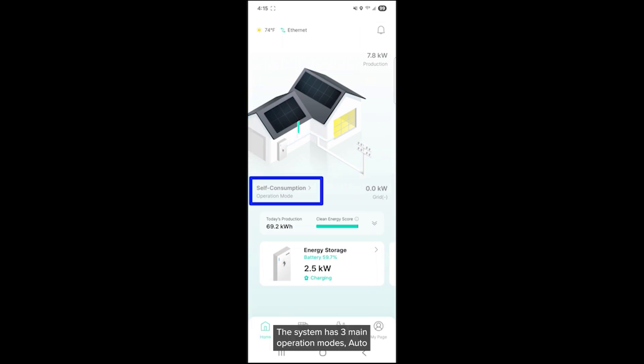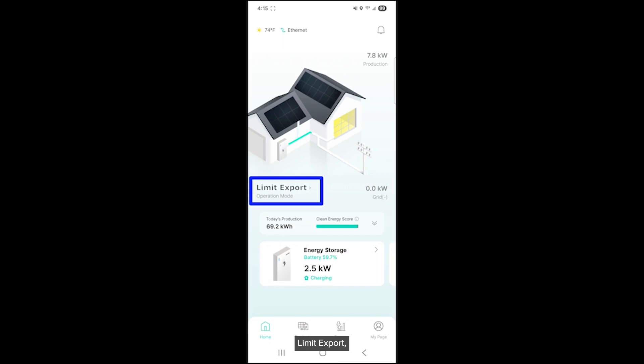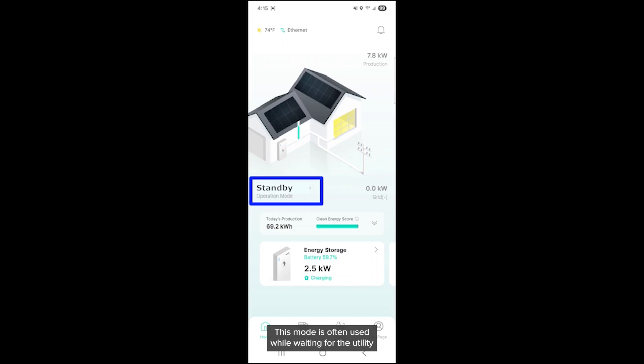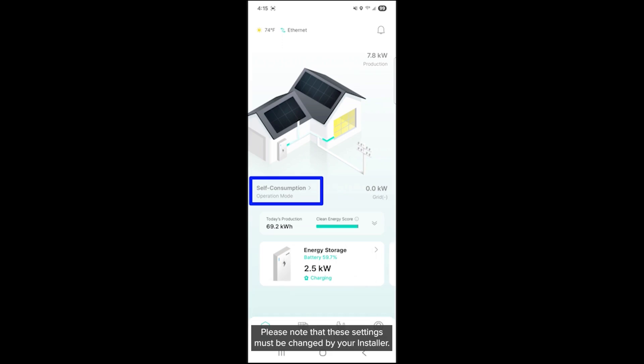The system has three main operation modes. Auto: The system is active and automatically managing energy flow. Limit export: The system is active and energy sent to the grid is limited to a certain threshold. Standby: The system is inactive. This mode is often used while waiting for the utility to provide permission to operate or PTO. Please note that these settings must be changed by your installer.